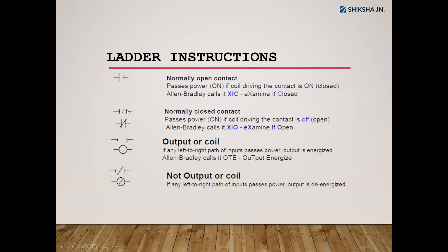Normally closed contact is the total opposite — it is already closed, and when you press it, it will disconnect the line. That is the difference between normally open and normally closed. The normally closed contact symbol has two lines on the side with one inclined line, or two intersecting lines. These represent similar things across different PLCs. The last symbol is the output coil, shown with open and closed brackets, representing all digital field instruments like motors, pumps, and solenoid valves — any digital on/off device.